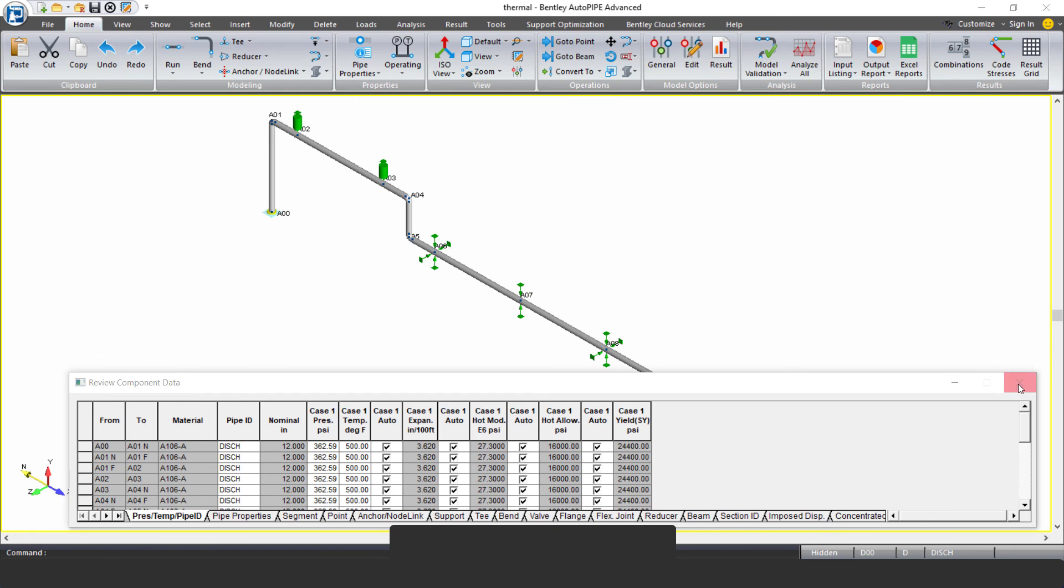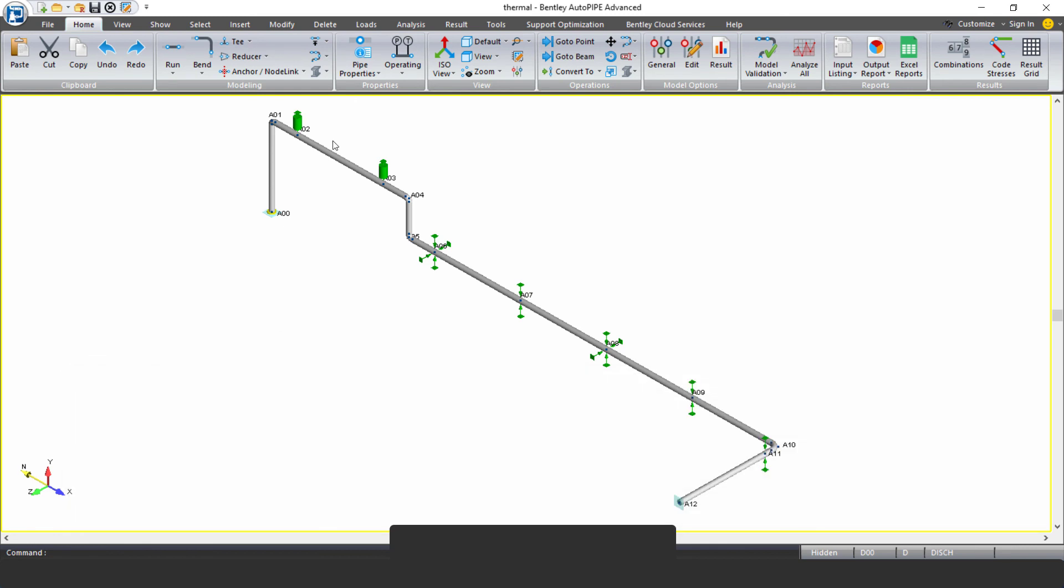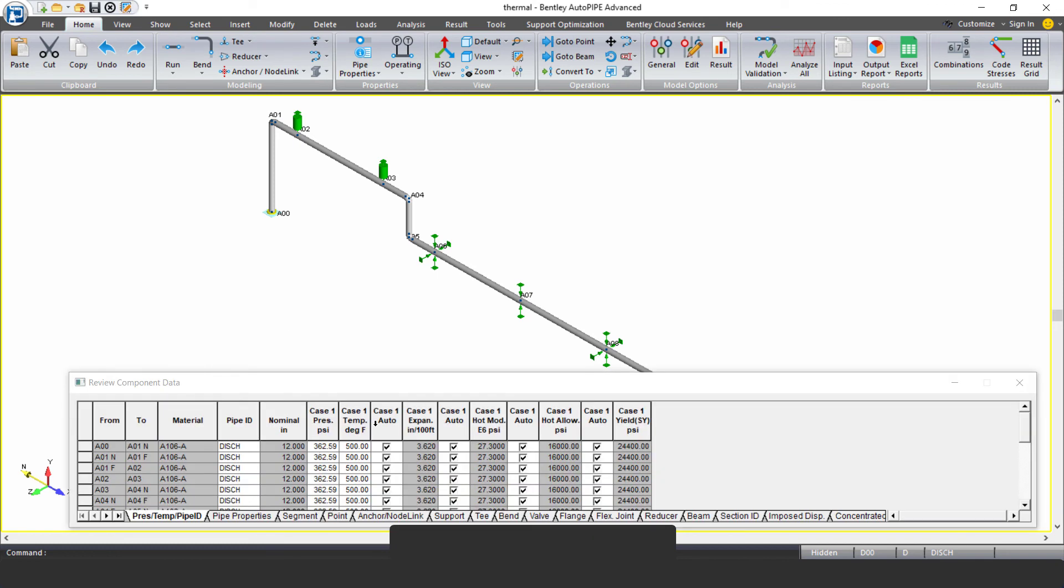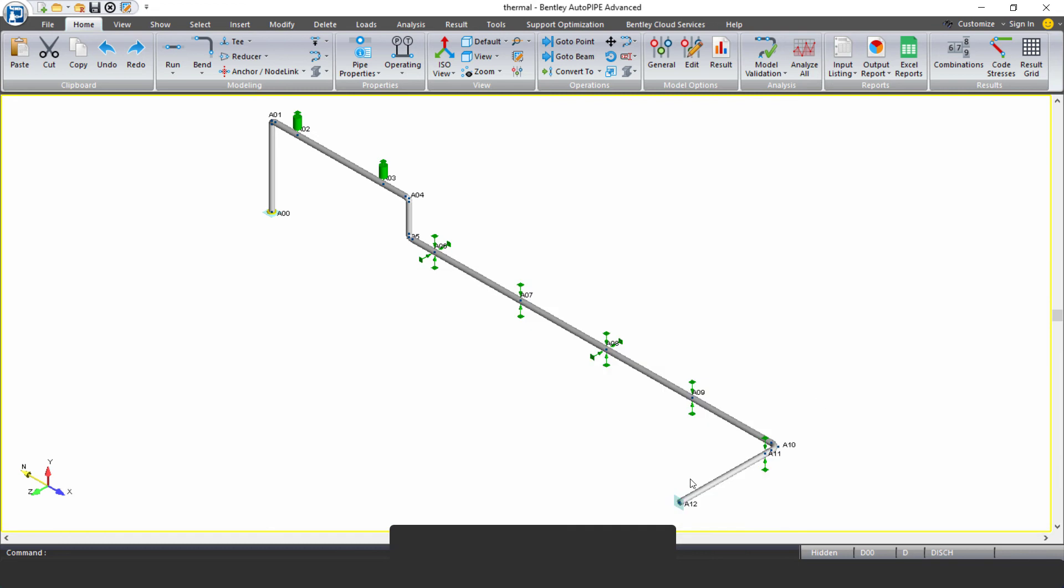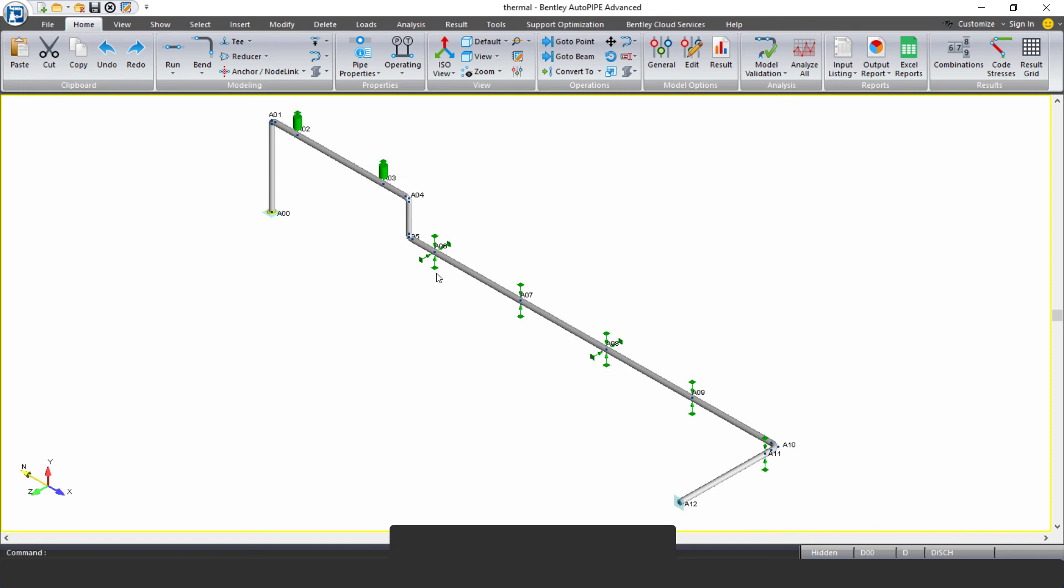So in this piping model, we just have a very simple pipe. If we look at our input grid here, we see we have some 500 degree Fahrenheit temperature, about 350 psi pressure, and we have hard piping throughout the whole model. We have some rigid supports, guides and vertical supports along the piping, but we have some variable spring hangers here that we're allowing the program to define for us to pick the correct spring figure and size for us from a manufacturer's catalog.